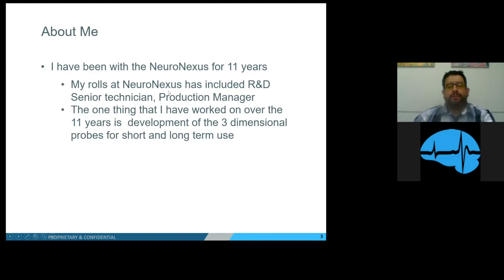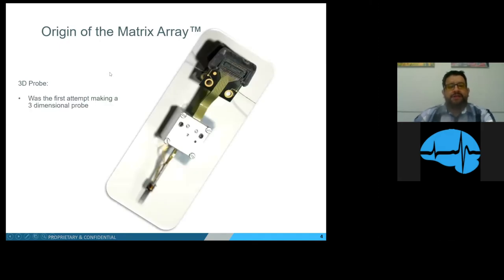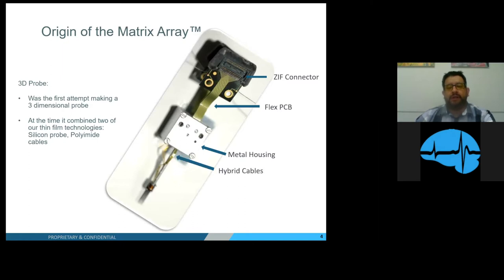In those 11 years I worked on helping develop the three-dimensional probe for short and long-term use. The origins behind the Matrix Array started with the 3D probe — it was our first attempt at making a three-dimensional probe. At the time we were combining two of our thin film technologies: silicon probe and polyimide cables. It had a ZIF or Omnetics connector, flexible PCB, metal housing, hybrid cables, guide rod, shim probe stack, and our silicon probe.